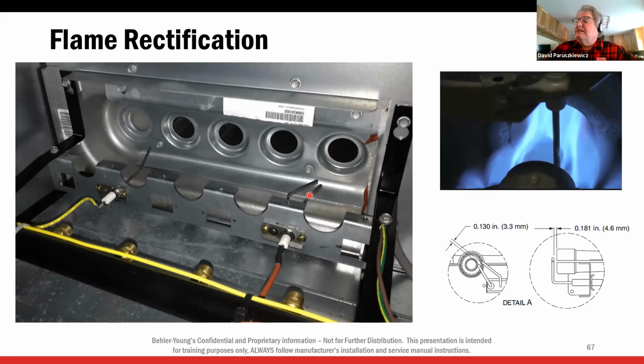Here's my igniter. Here's my ground. So I make a spark right here. Once it starts sparking, the gas valve opens. This burner lights, hopefully lights this burner, this burner, this burner. Once we carry across, we get a flame established. The flame picks up the current from the flame rod and carries it to the ground. All right. So if that last burner doesn't light, we can't get a flame signal.